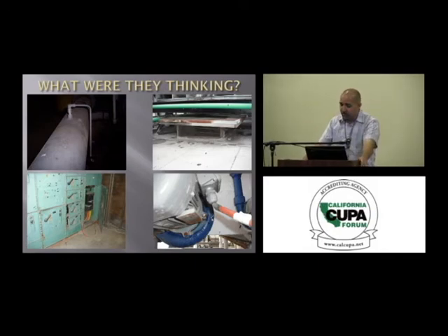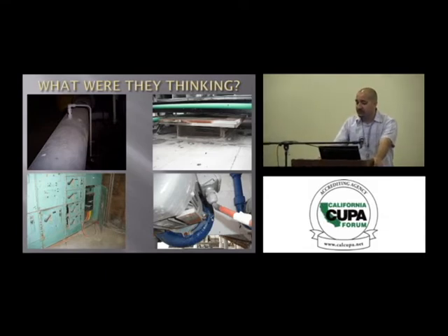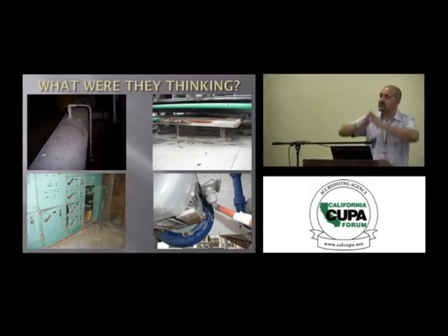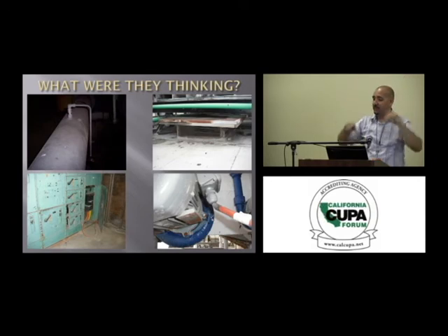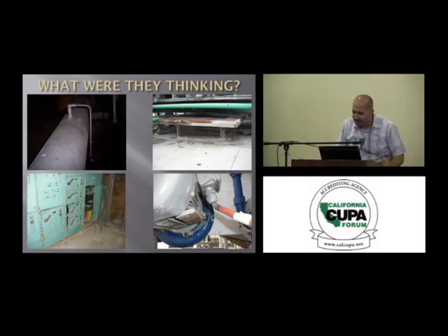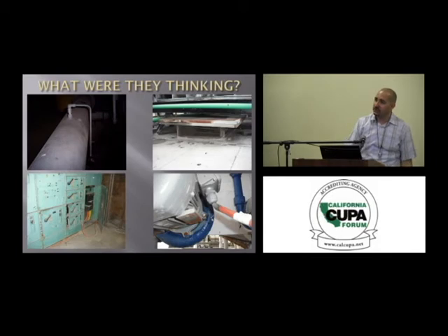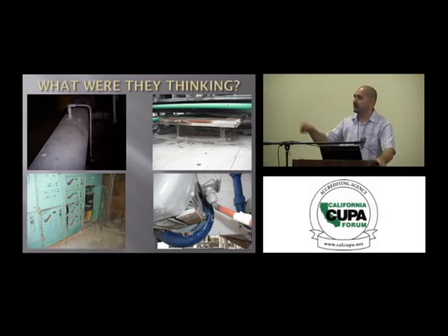As you can see on the right-hand side, we have your emergency exhaust fan. That needs to be venting straight on up to the top. As you can see, it's got a top on it, and it seems to be under a condenser. So it could hit and not go anywhere. It might circle back around to the inside vents coming into the compressor room while you're trying to hit that emergency exhaust vent to move the ammonia, and it's just going to circle around, and you're going to get yourself in trouble. So making sure that it's properly installed.